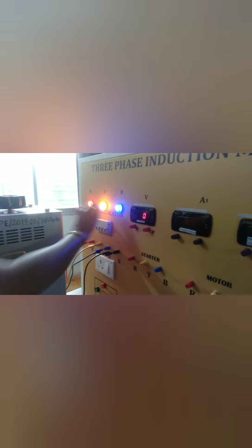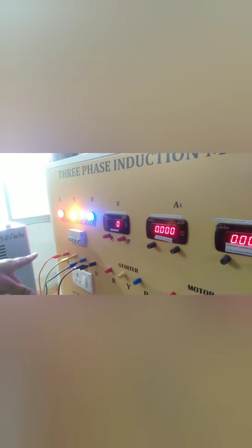Now we have already blocked the rotor, and we have to take the reading for block rotor of the 3-phase induction motor. As you can see, supply is on, all 3 lights are on. Now we have to give the supply voltage and increase the current up to 7.1 ampere. Why 7.1 ampere? Because the rated current is 7.1. So this is the rated current. We need to go till 7.1, and in that way we have to take the reading.